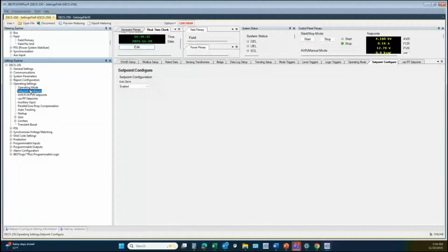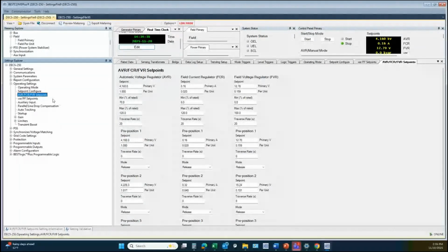And then we get to the actual set points themselves. As you can see, I had changed the rated data earlier, and now my AVR set point reflects that. So it's now at 4160. Most of the time you set the minimum probably a little tighter than 70%, or perhaps you prefer the 70%. But a lot of applications prefer plus and minus 10%, and those percentage values are going to be based upon that rated voltage value that I previously set. The traverse rate is how fast it will transition from one extreme to the other when you're holding the raise and lower, so you can slow or speed up that transition.